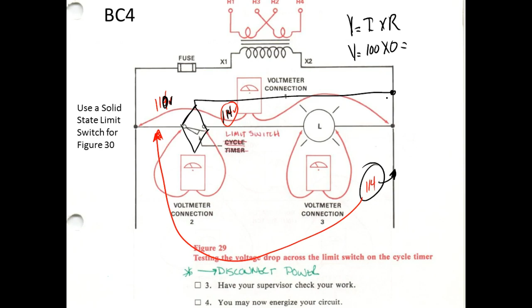But these solid state limit switches, these inductive limit switches, and these capacitive ones, they take almost no power to operate. So that means we can power these guys up through the load. Does that make sense? They still drop a voltage, but not enough to hinder the operation of the load - it's well within the limits.